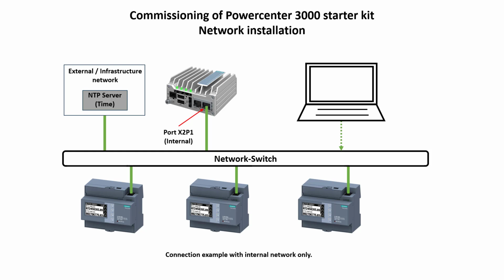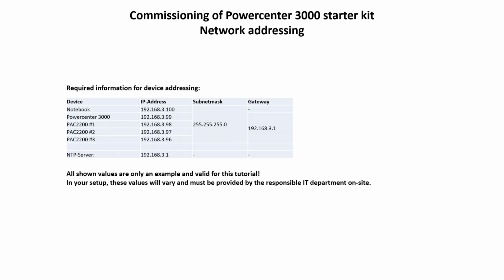If the network infrastructure is ready and all devices are connected and powered, we can start commissioning by connecting a notebook with Windows operating system to the network. Please ensure that the connection to Powercenter 3000 is done via the internal port. A connection via the external port will not work by default. For preparing, it must also be clear which network addresses fit your network. In this tutorial, I use these addresses, which you can take as an example.